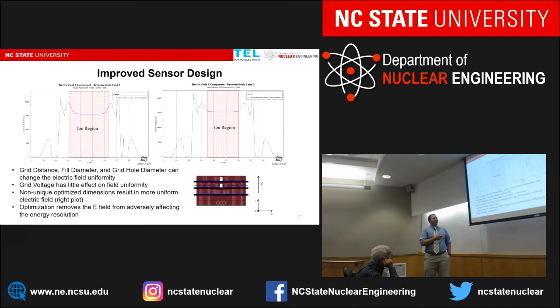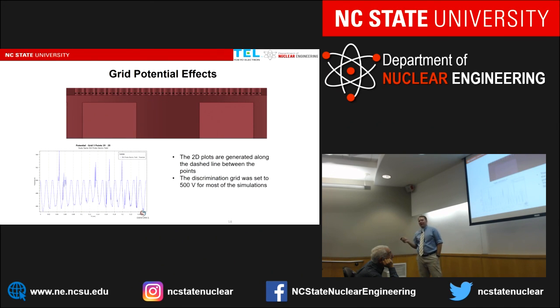So we can move on to look at something that has more effect on the actual energy resolution, which is the potential in the grid holes. Ideally, when we take an RFEA measurement, we think the potential we apply across the metal grid is going to be the same within the grid holes as well. However, based on the simulation, you can see here in the plot, there's a drop in potential anywhere from possibly 5 volts to 3 volts in this case, where we're taking the potential at this dashed line here, as this was the point where the difference between what was applied to the grid and what was in the holes was minimized. And in this instance, we just applied 500 volts across this actual grid. So what does this mean?